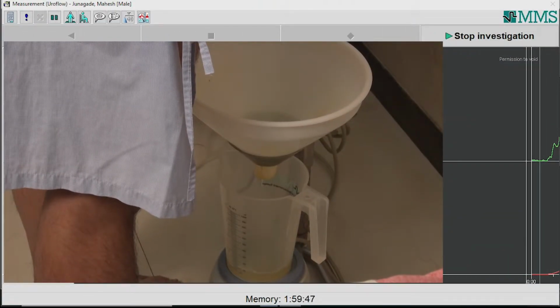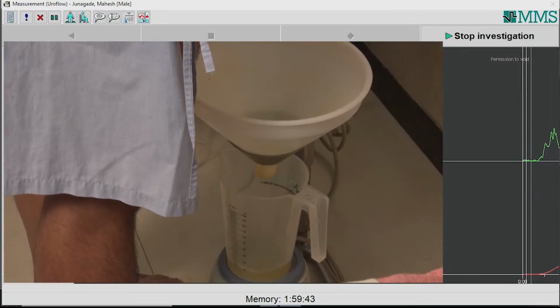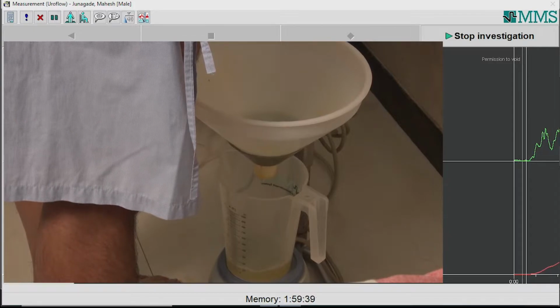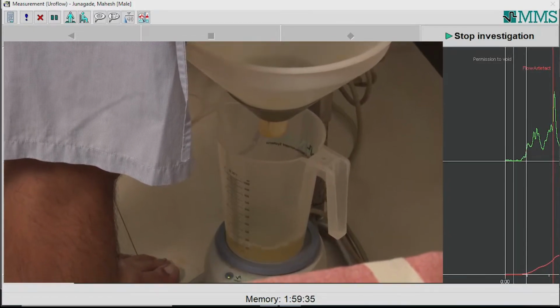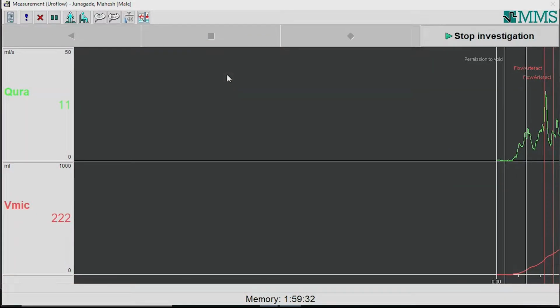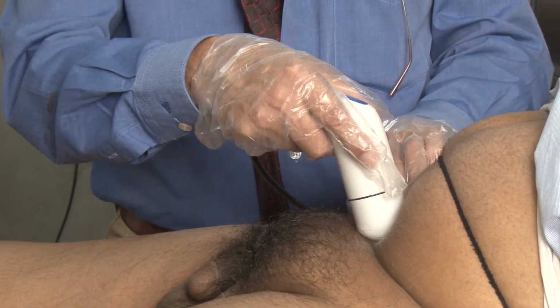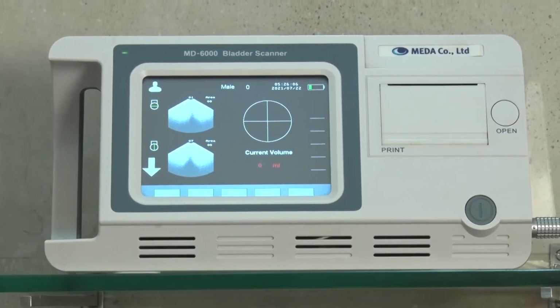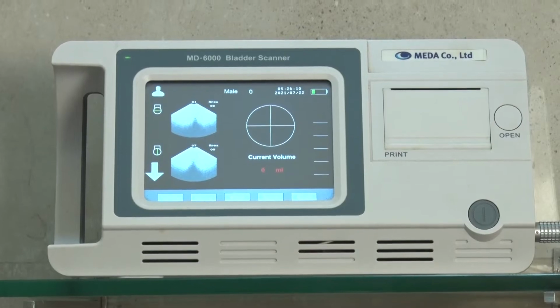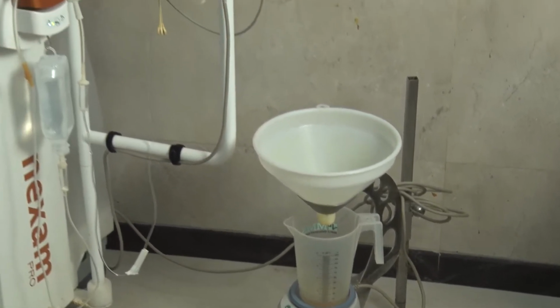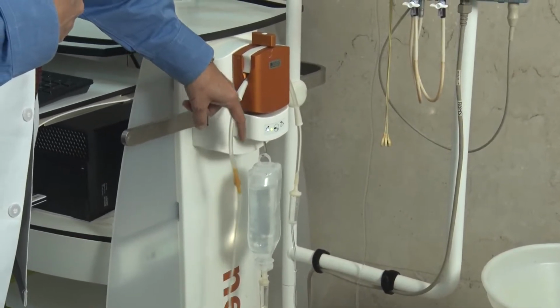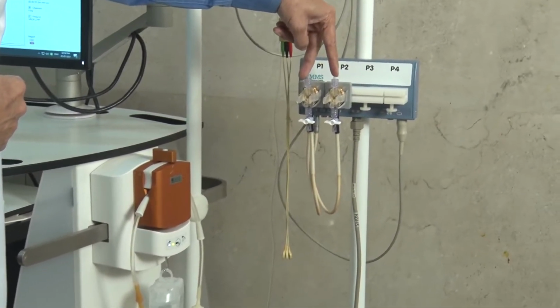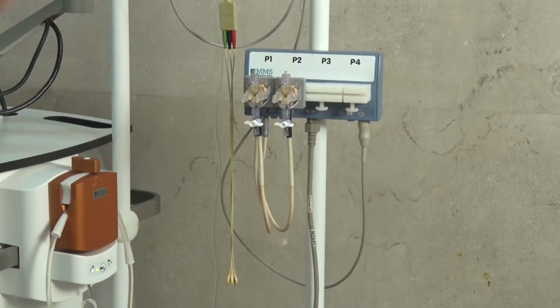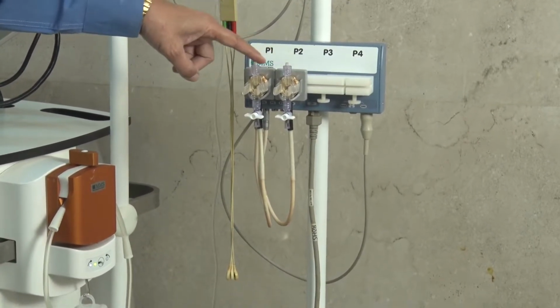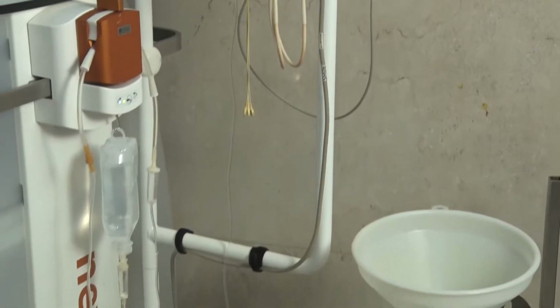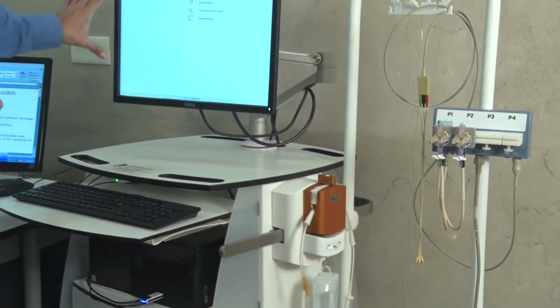Uroflowmetry is the simplest and the most basic investigation that gives us a platform from which other tests can be interpreted. All other values can then be interpreted taking into account the catheter-free test of the patient's urinary flow rate. This is generally followed by an ultrasound measurement of residual volume by an instrument called a bladder scan. That's the flow transducer, which measures the urinary flow. This is the infusion pump, which pushes saline into the bladder at a set speed. These are electronic pressure transducers, which measure accurately the intravesical and rectal pressures.